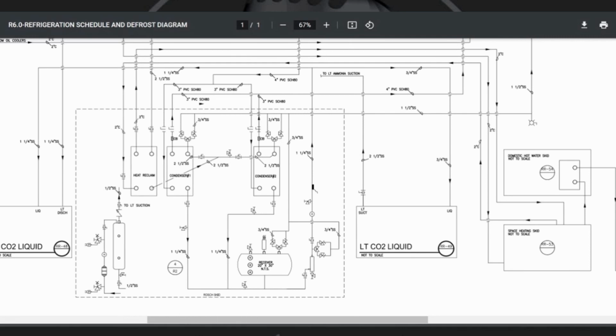No, no. What really happened is, think about that vessel half full of liquid. You have a temperature-pressure relationship, right? If you don't vent it, then that receiver will warm up, and at 85 or 90 degrees you're going to have 165, 170 pounds of head pressure. And so it would back the liquid up into the condensers, and we couldn't get the head pressure down.